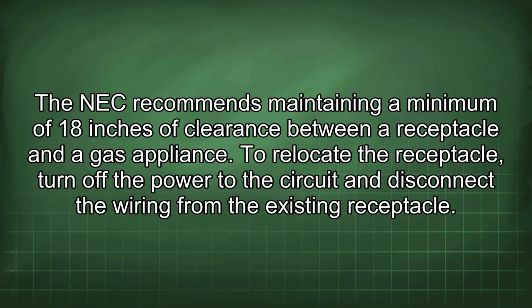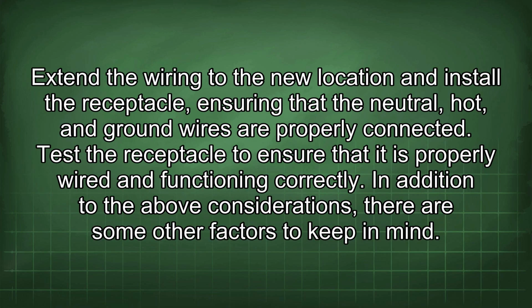The NEC recommends maintaining a minimum of 18 inches of clearance between the receptacle and the gas appliance. To relocate the receptacle, turn off the power to the circuit and disconnect the wiring from the existing receptacle. Extend the wiring to the new location and install the receptacle, ensuring that the neutral, hot, and ground wires are properly connected. Test the receptacle to ensure that it is properly wired and functioning correctly.